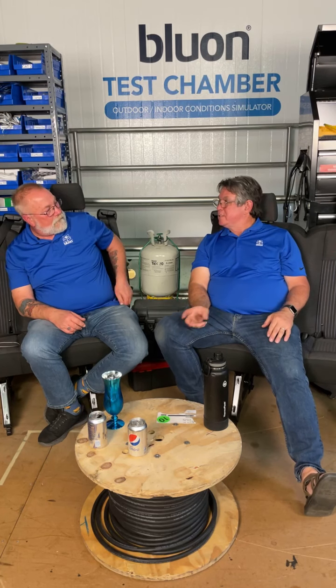So, one of the things, and I'll just hit this real quick. People ask the question, why do compressors fail? I don't know. And that's so untrue, because compressors fail for basically two reasons, mechanical or electrical. And if you have too little superheat, you could be flooding liquid back to the compressor and you can't compress a liquid. Depending upon how much liquid's there, something's going to give. Bigger compressors, it's usually rods coming out the side of the crankcase. Smaller compressors, they lock up and they break. Real high superheat, you're overheating the windings, and as a result, the lacquer can break down.